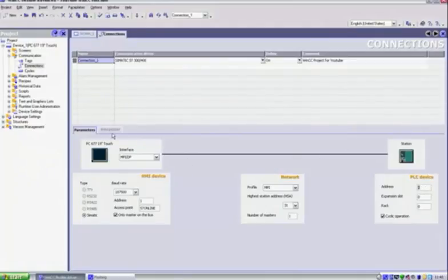Siemens always defaults that to 2 because, and I said at the time on that video, that HMIs will normally be 1, and your PC, your laptop or your computer that's connected to the system, you will set up as address zero. So that is kind of your master on the system. Laptops and connection devices such as laptops or desktops are default to address zero. The address on the HMI, MPI or DP, will default to one, and all of your PLCs default to two. And then what that does is it allows you to use 3, 4, 5 and upwards for any external devices such as DP couplers, or inverters, or anything else that you might be using at the time.